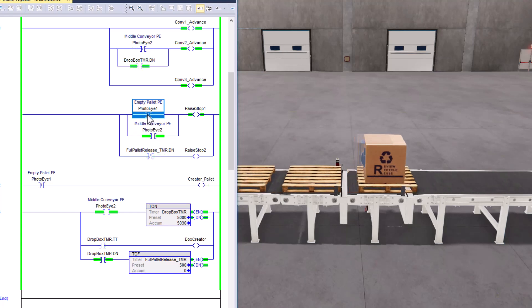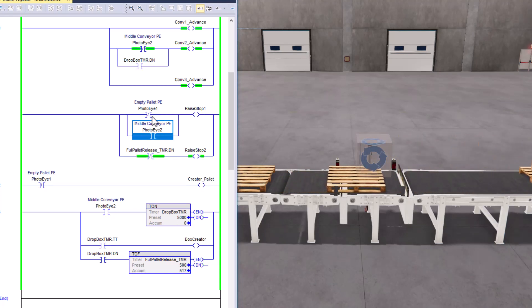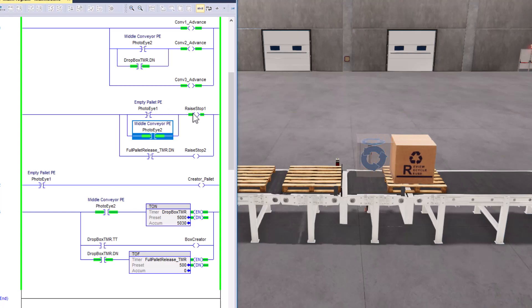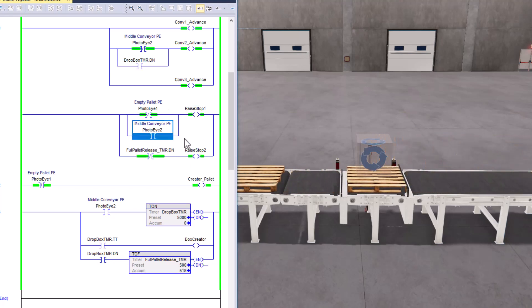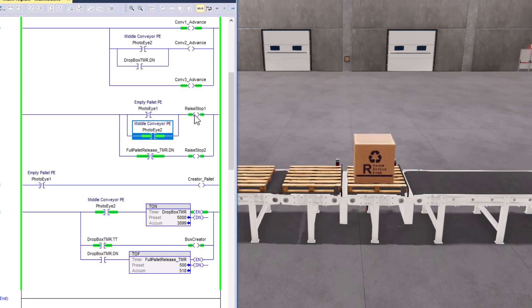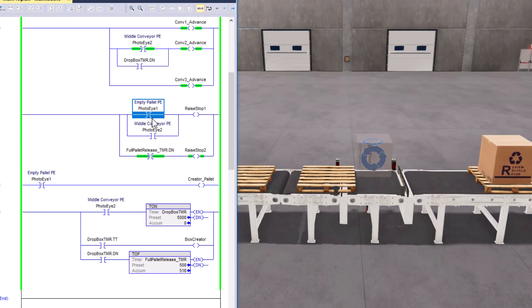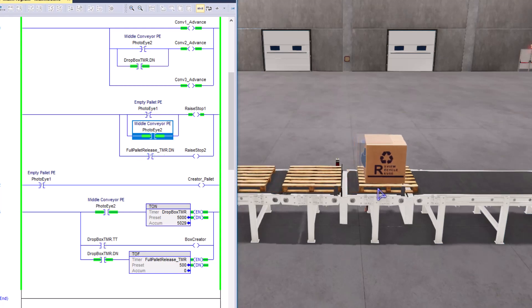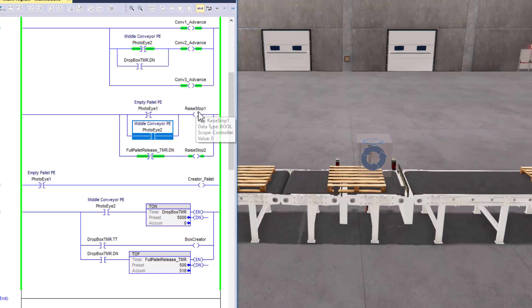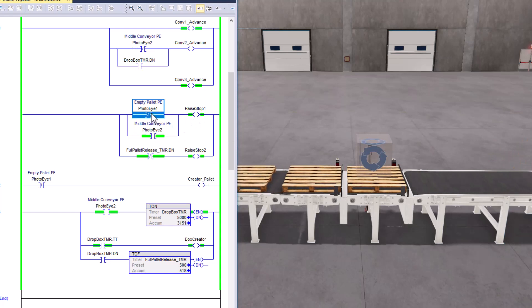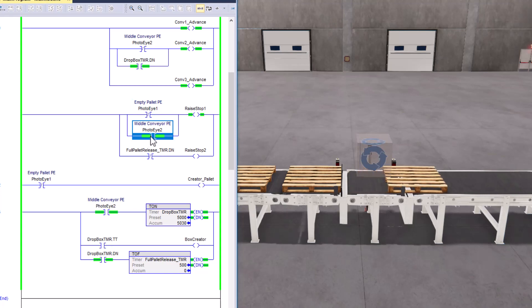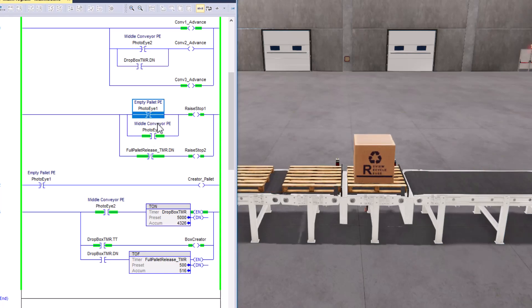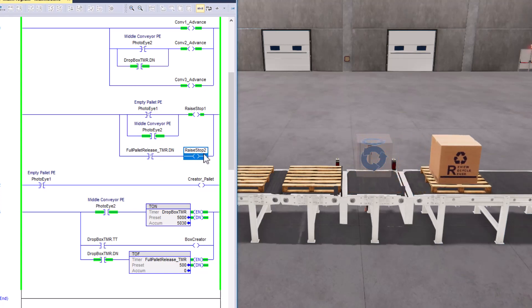Now let's talk about controlling the stops. Photo Eye 1 is right here — as soon as it's made, it drops that stop. For Stop 1, it's an OR situation in parallel — either condition can control the stop. If Photo Eye 2 is made we keep Stop 1 up, and if there's no palette detected in the second section, we also allow the stop to raise.